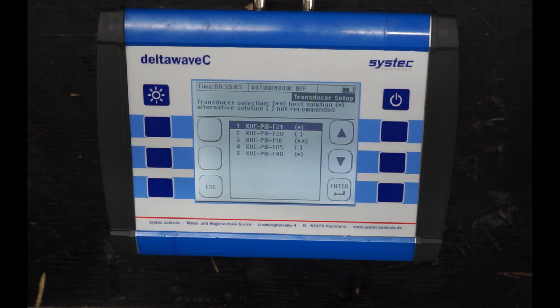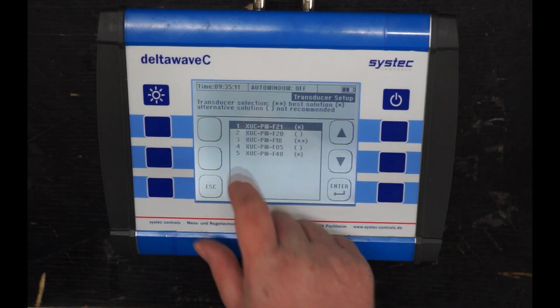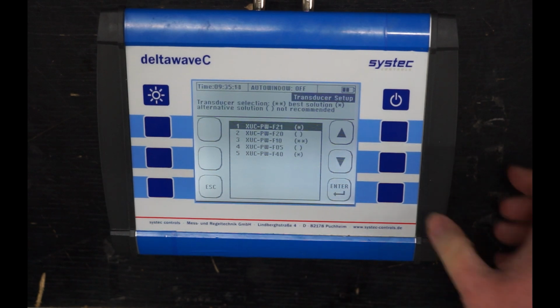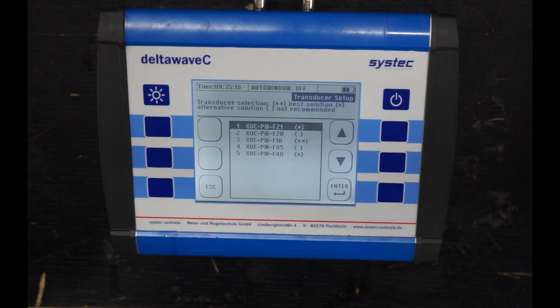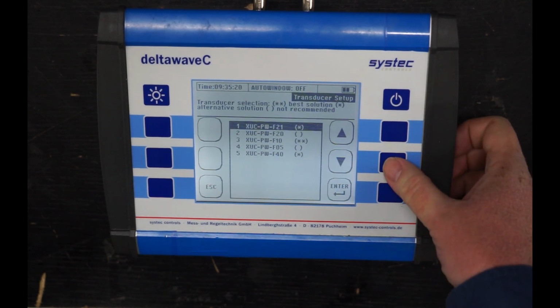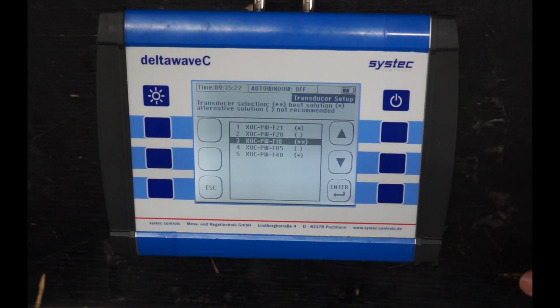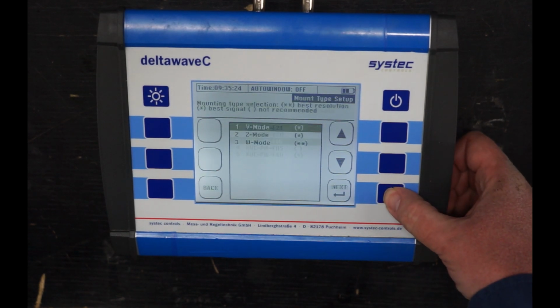deltawaveC offers 3 different transducers to cover all pipe sizes between 10 millimeters and 6 meters in diameter. Depending on your previously chosen diameter, deltawaveC will give you a suggestion which transducer will work best for your application. The display will indicate the best solution with 2 stars and a good alternative with 1 star. I will choose option 3, which is considered the best solution for my application.